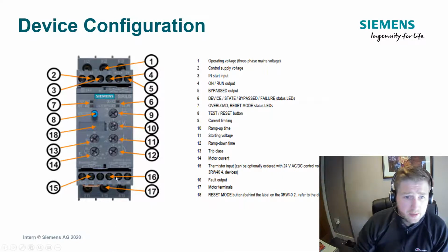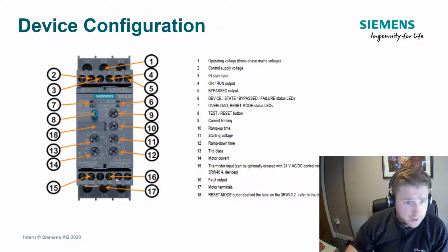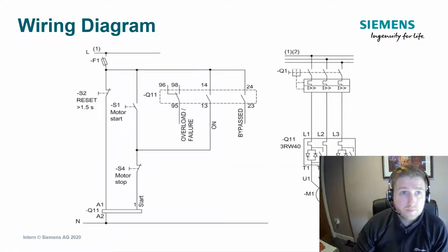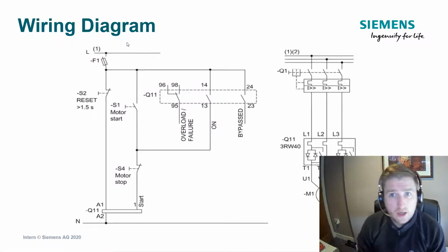And then this last terminal here, terminal 16, is another signaling contact for a fault, which you might want an illuminated push button to raise an alarm, say for anything that was untoward, or something was flagging up on the soft starter which was in the control cabinet. You might want to view something on the front of the control panel instead. So on this next slide, it just gives you a bit of an idea as to how you'd wire the soft starter. It's very, very similar to the 3RW30 in terms of the configuration, except it has a couple more features on there in terms of signaling.